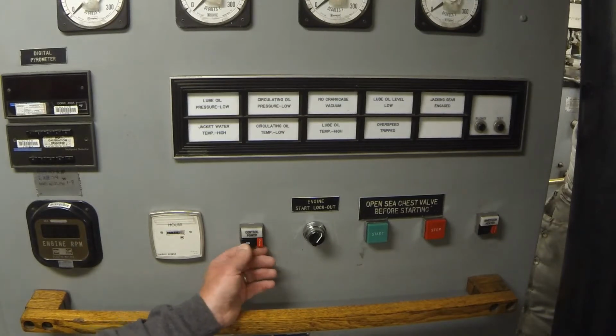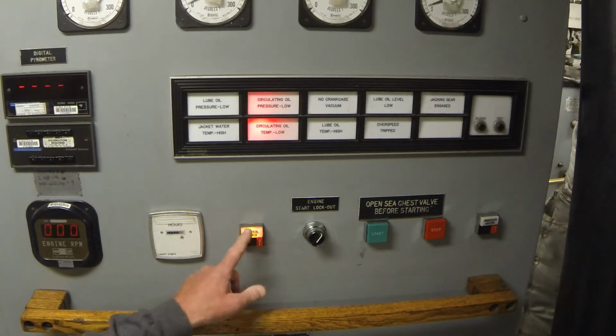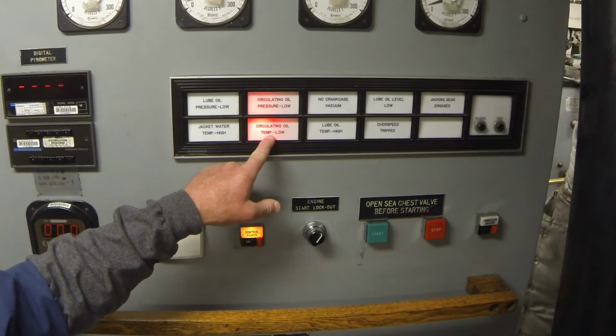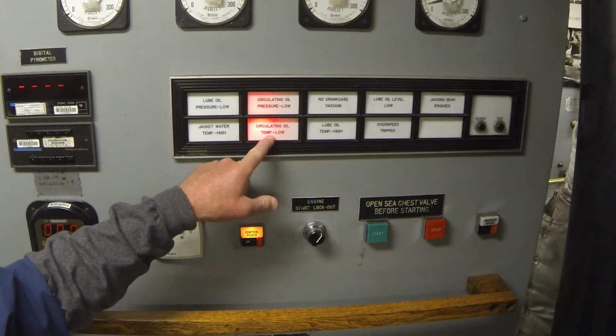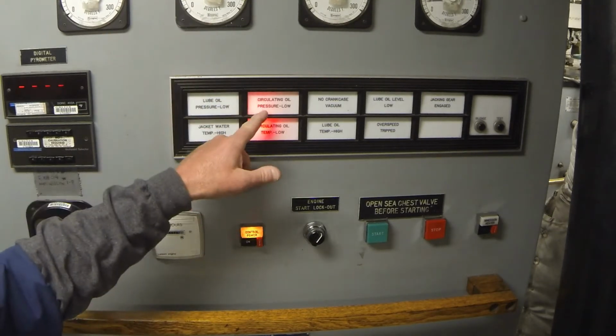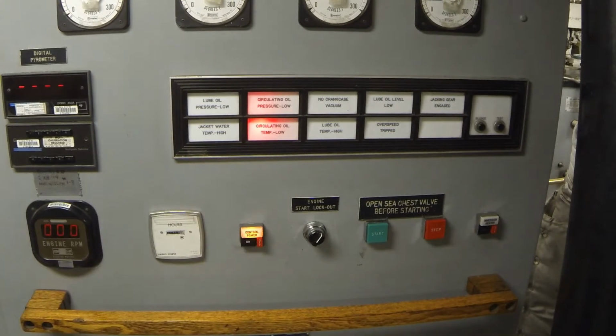Once I have that immersion heater in operation, it's always a good idea to turn on my control power. I'll see circulating oil temp low, which is normal because the oil temp is low, and I also see circulating oil pressure low. Now once that circulating oil pump's in operation, I would expect this alarm to extinguish within a minute. And there it goes. So what that is showing me is that I do have oil pressure circulating throughout the engine right now. Not in the upper gallery because the prelube valve hasn't been opened yet.